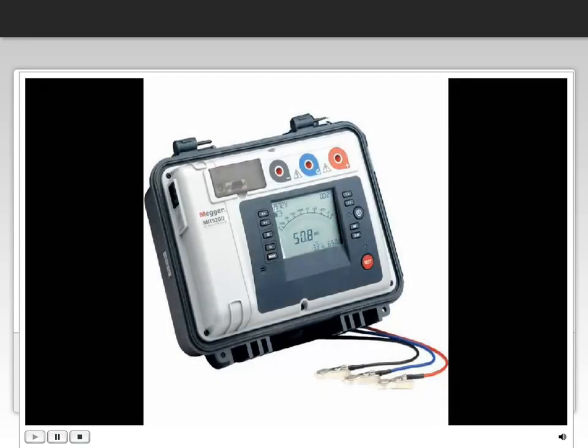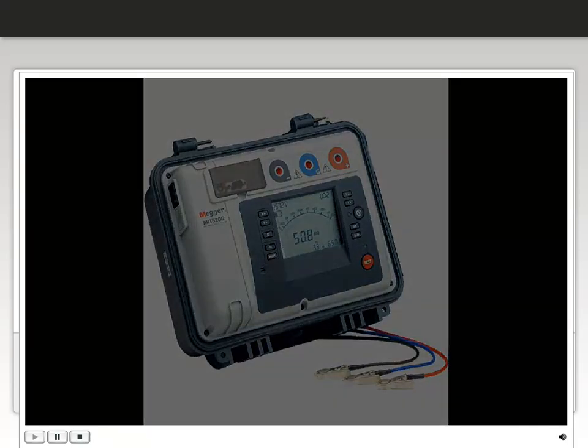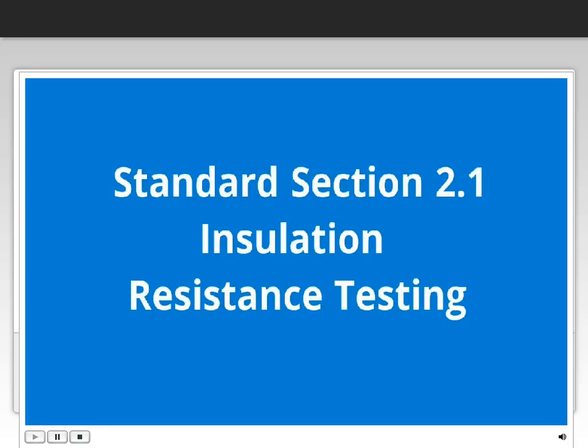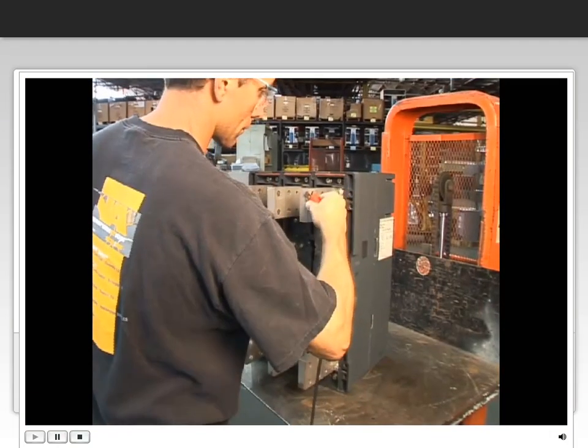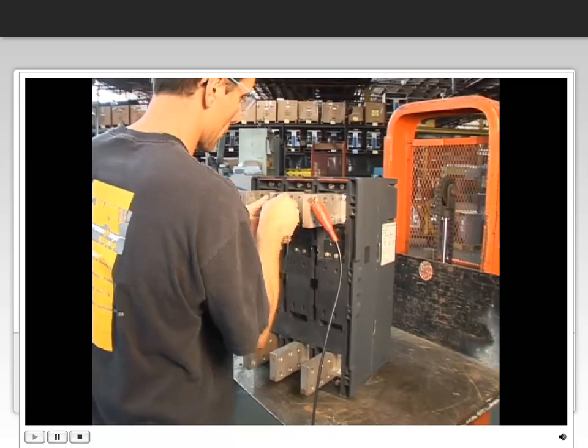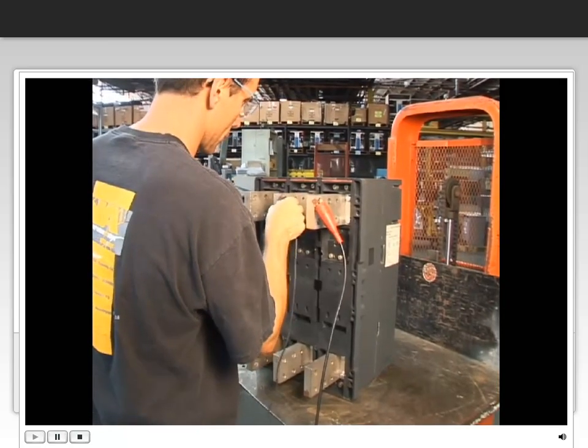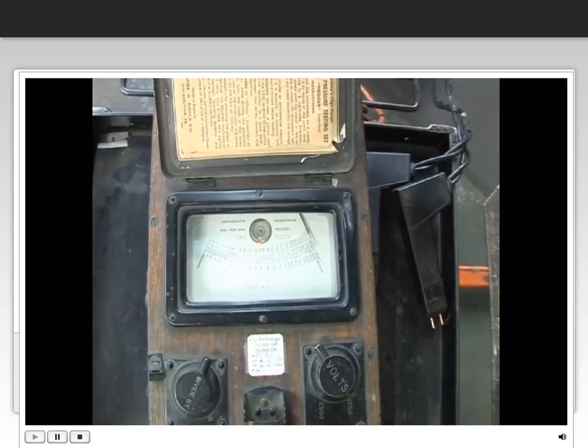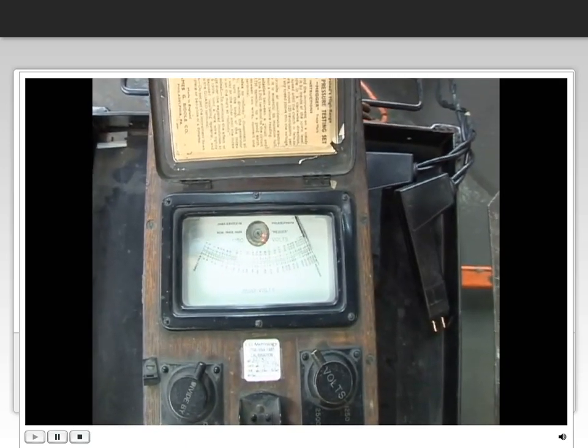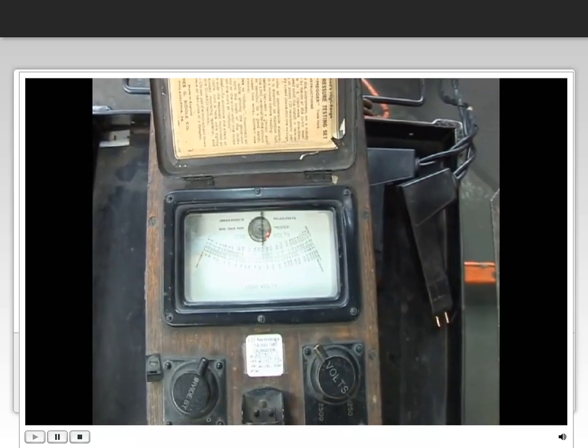This breaker will be tested with a 2500 volt megger. With the breaker open, this test checks the integrity of the insulation between each of the 6 main stabs and the breaker frame. The insulation from line and load side on the same phase are also checked. With the breaker closed, the test checks the resistance between the main line stabs and the frame. The phase-to-phase insulation is also checked.